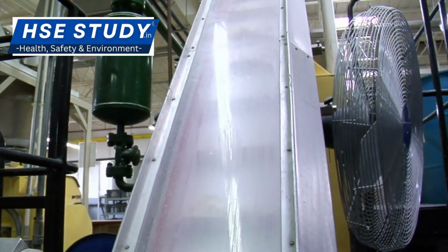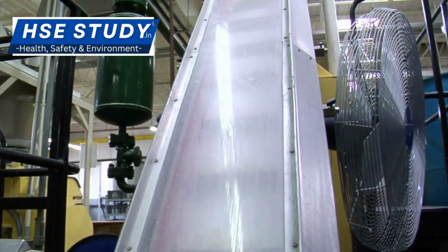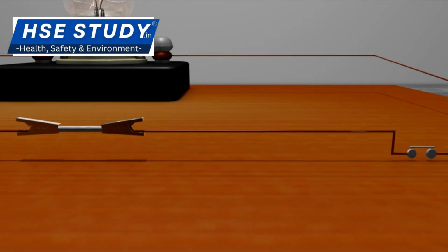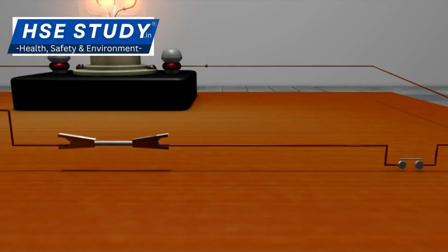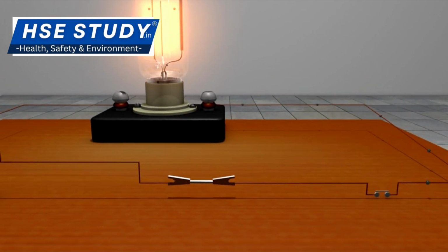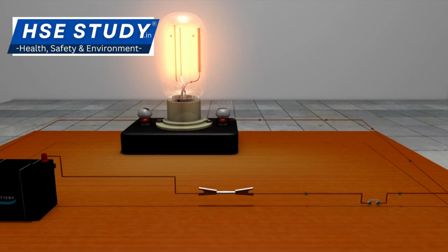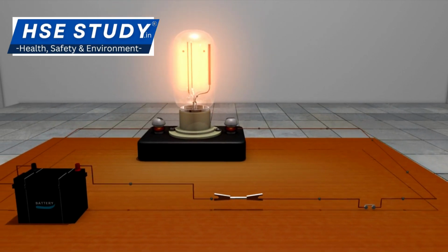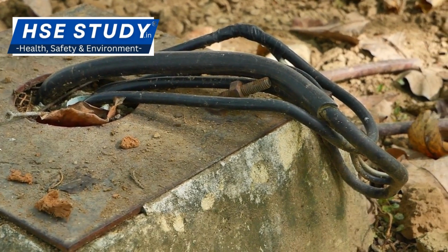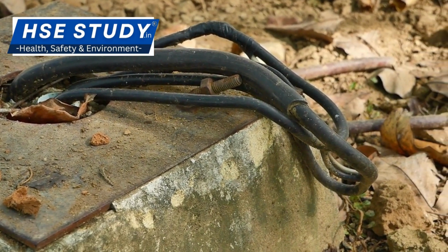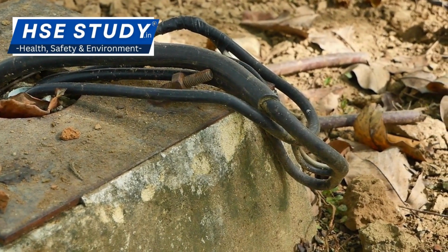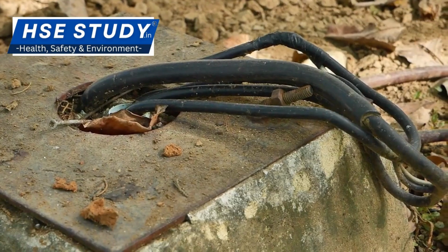For example, a plastic conveyor belt rubbing against a roller can generate enough static to ignite a gas cloud. Clause 6.2 recommends using conductive or dissipative materials instead, like metal or anti-static plastics with surface resistivity below 10 to the power of 9 ohms per Table 1. Earthing these materials as per Clause 6.2.3 is non-negotiable. Connect them to ground to drain charges safely, reducing spark risks by 90% per industry studies.